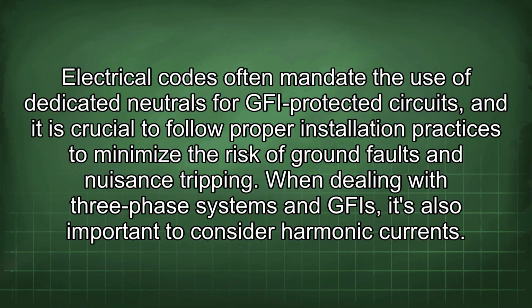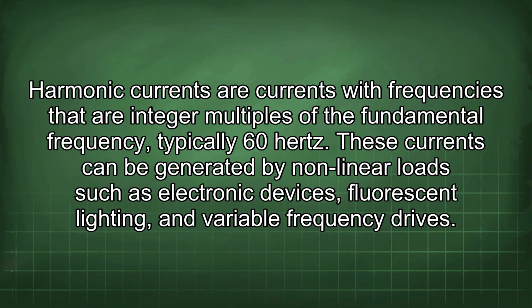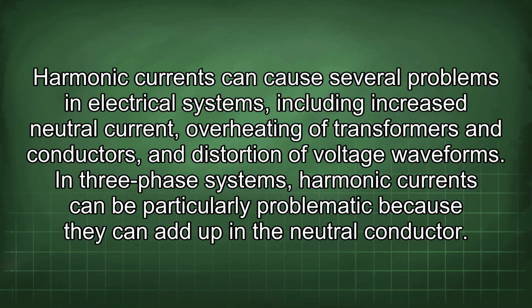When dealing with three-phase systems and GFI, it's also important to consider harmonic currents. Harmonic currents are currents with frequencies that are integer multiples of the fundamental frequency, typically 60 Hz. These currents can be generated by nonlinear loads such as electronic devices, fluorescent lighting, and variable frequency drives.